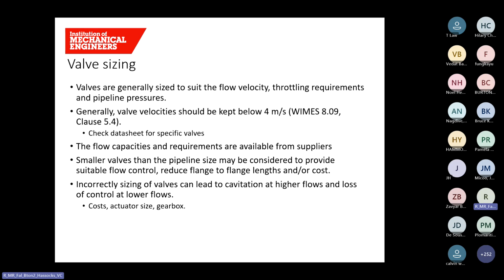If you don't size the valve correctly, it can lead to cavitation occurring. So if the velocities are too high past the valve and you're trying to throttle with it, then it can cause cavitation. And also, if the valve is too large, then you can't get the control that you're after, because the point at which the valve can achieve the control is usually at the almost closed position, and there's not much modulation on the control there.